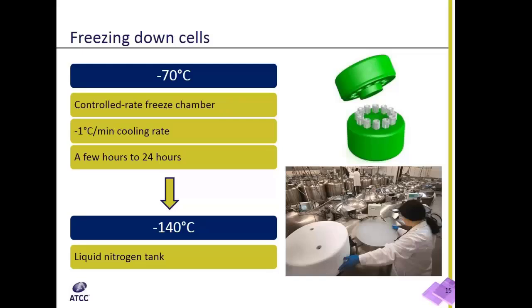Cells must be cooled at a rate of about minus 1 degree per minute in a freezer at minus 70 degrees Celsius. This is achieved with the use of a controlled rate freezer or controlled rate chamber.